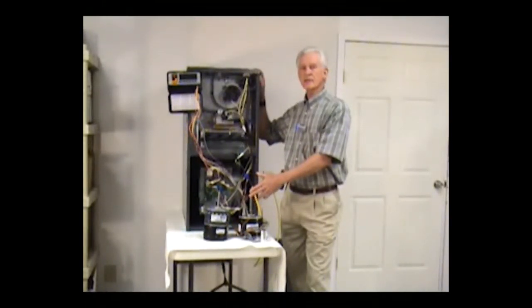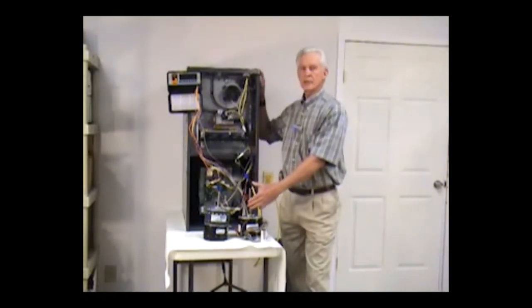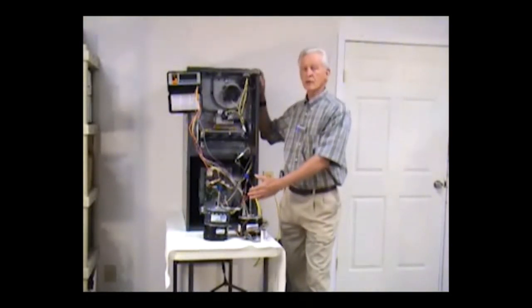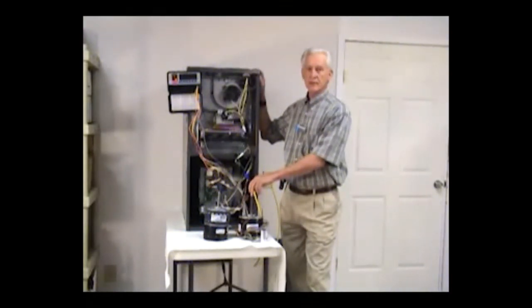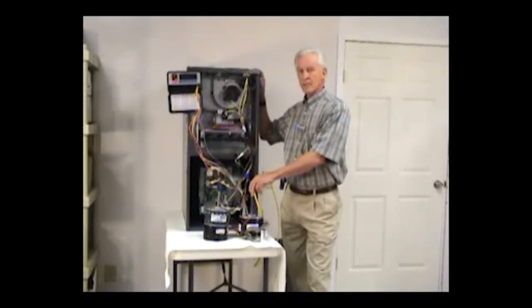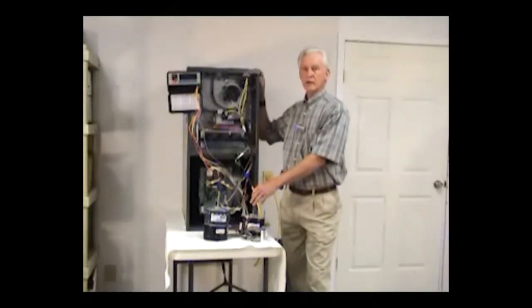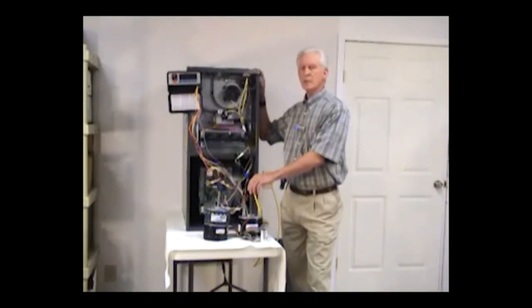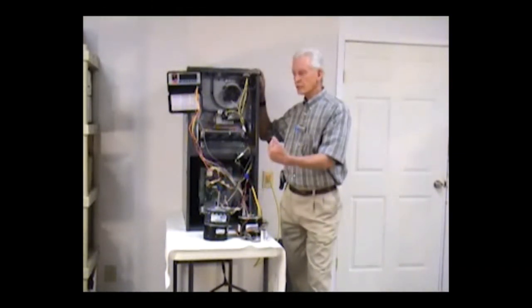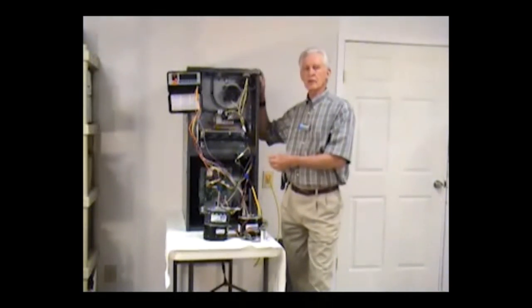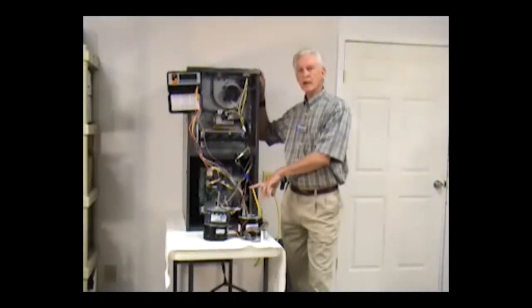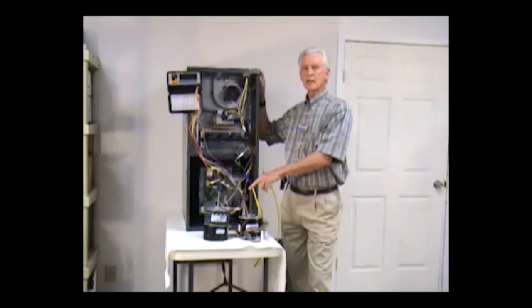Horsepower at that particular stage of the game is important, so we end up with either quarters or thirds or halves, three quarters, and in some cases with residential applications, we will even have a one horsepower motor. But whatever that application, in this particular case, we'll say that this one has like a third horsepower motor in it. That third horsepower motor, with the load that it has against it, will produce a given amount of air for the tonnage that we're talking about. Lots of times third horsepower motors is going to be in the neighborhood of a 3-ton application. So we're talking about, in that case, 1200 CFM of air.